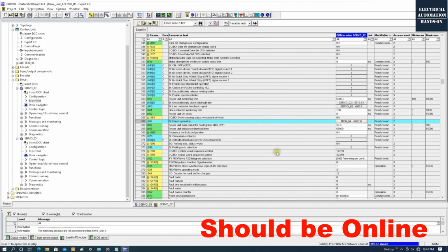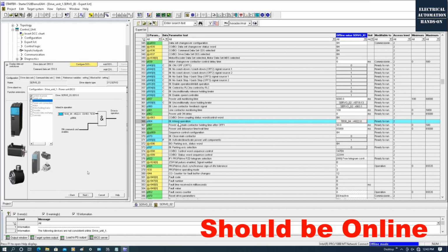Let's pick this. So it's in-feed operation. Let's use this TB30 R4022.0. If you recall, when we did configuration for the Servo 3, we did the same thing. We configured the in-feed operation connect to TB30 R4022.0. That allows the in-feed operation ready signal as one of the conditions to enable our drive power. So if the in-feed has something wrong, this enable signal will be off. So the drive will not be powered.